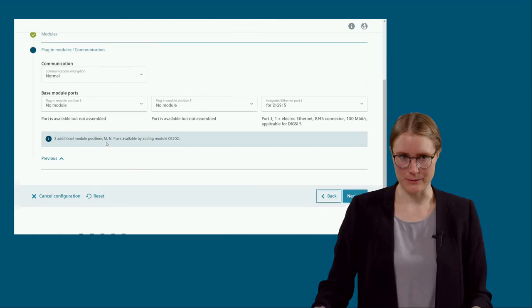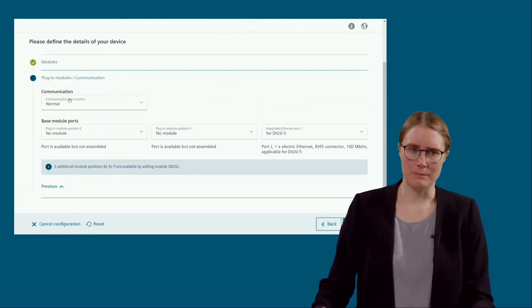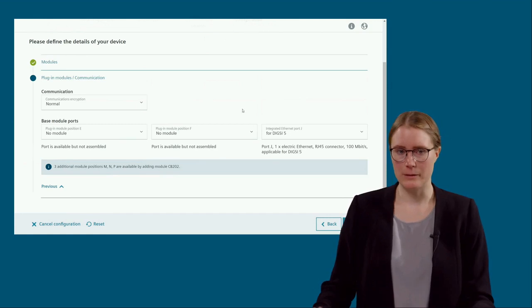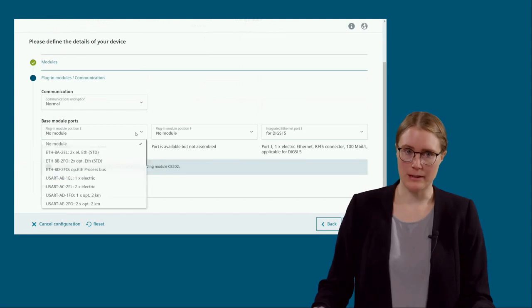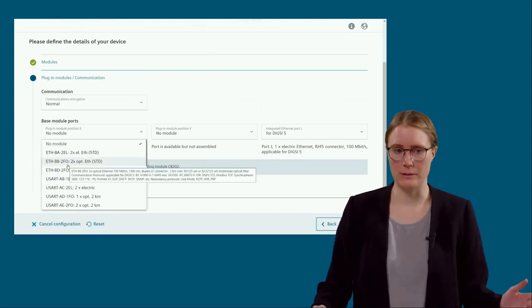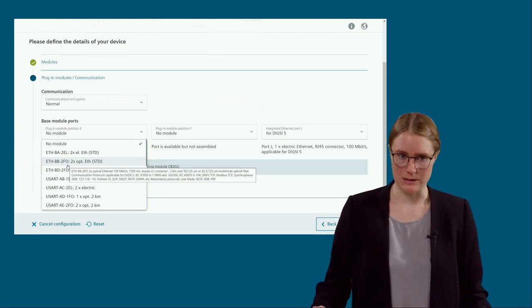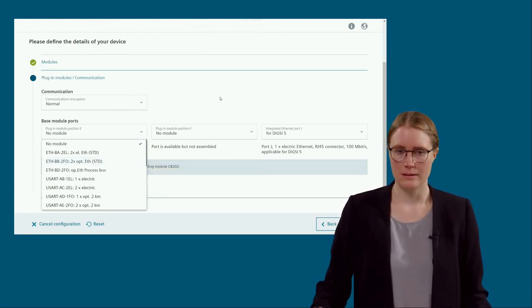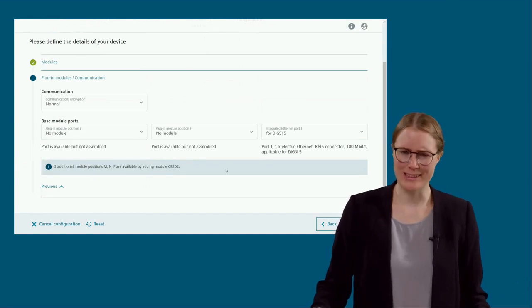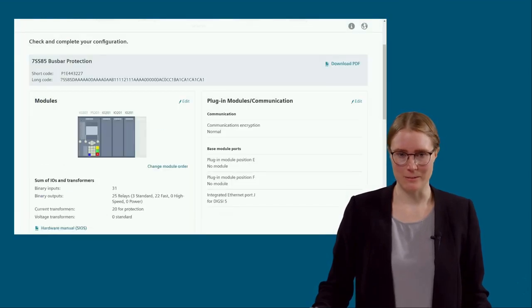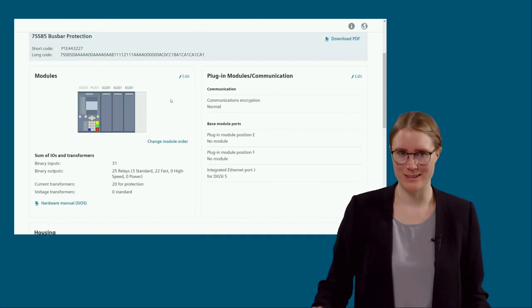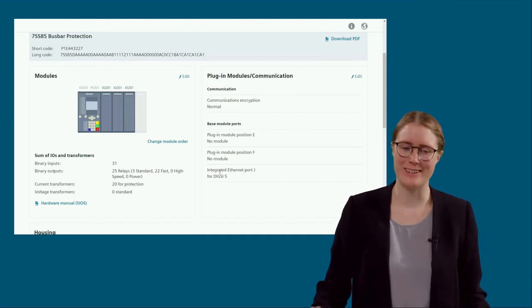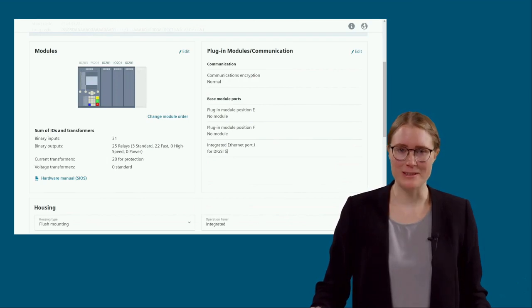And this is where you have the possibility to select the plugin modules for communication. At the moment, no module is available here. You can, for example, add an additional module, like an Ethernet BB module for your substation communication. In our case, I just leave it like that and jump to the next step. Here, once again, a nice overview. What do we have selected in our basket already? What modules are there? What expansion modules are added?